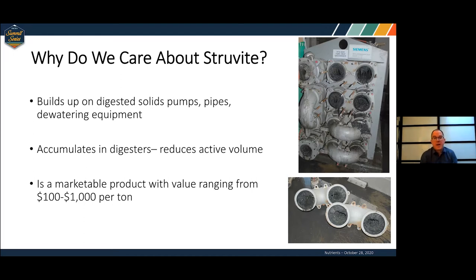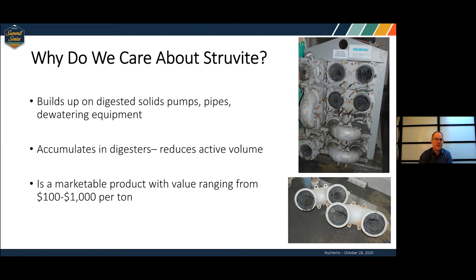What does struvite do and why do we care? It just builds up — in pipes, on pumps. You can see pictures of a heat exchanger completely clogged. It can accumulate in digesters. You may think you have a million gallons of digester, but actually only 750,000 gallons because the rest is all struvite — it can really reduce your active volume. On the other hand, struvite could actually be a valuable resource, since the nutrients are good for fertilizer. Depending on the form, you can market it for $1,000 to $2,000 per ton.